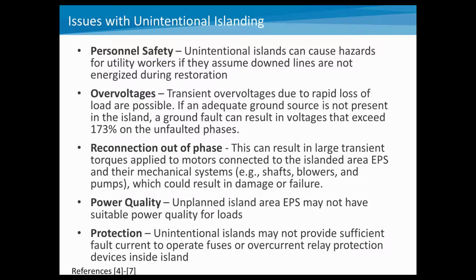And then power quality: within any unplanned island, your distributed generation may not be able to provide suitable power quality for the loads. And then finally, protection issues. If you have an unintentional island, you may not be providing enough fault current, for example, to operate fuses or overcurrent relay protection inside the island. And so your protection systems may need to be adjusted. There's a variety of references you see on the bottom and then listed at the back end of the presentation.